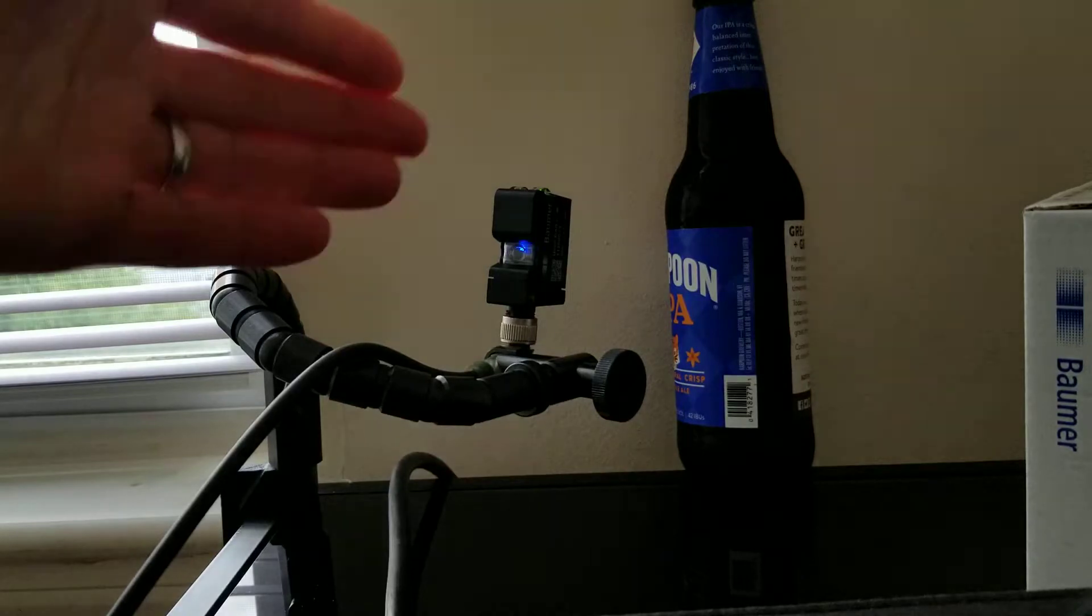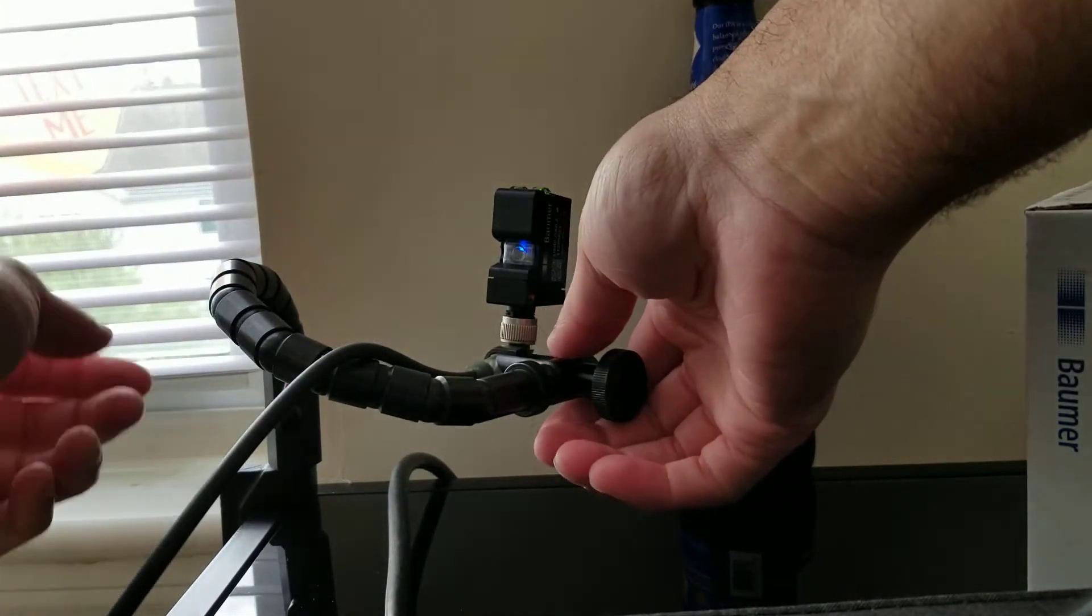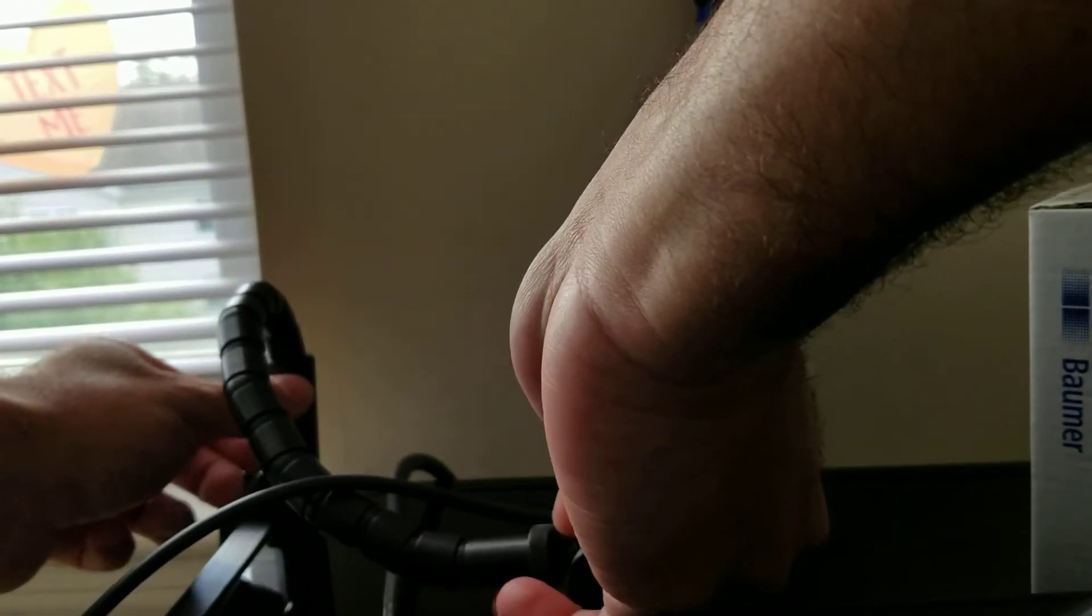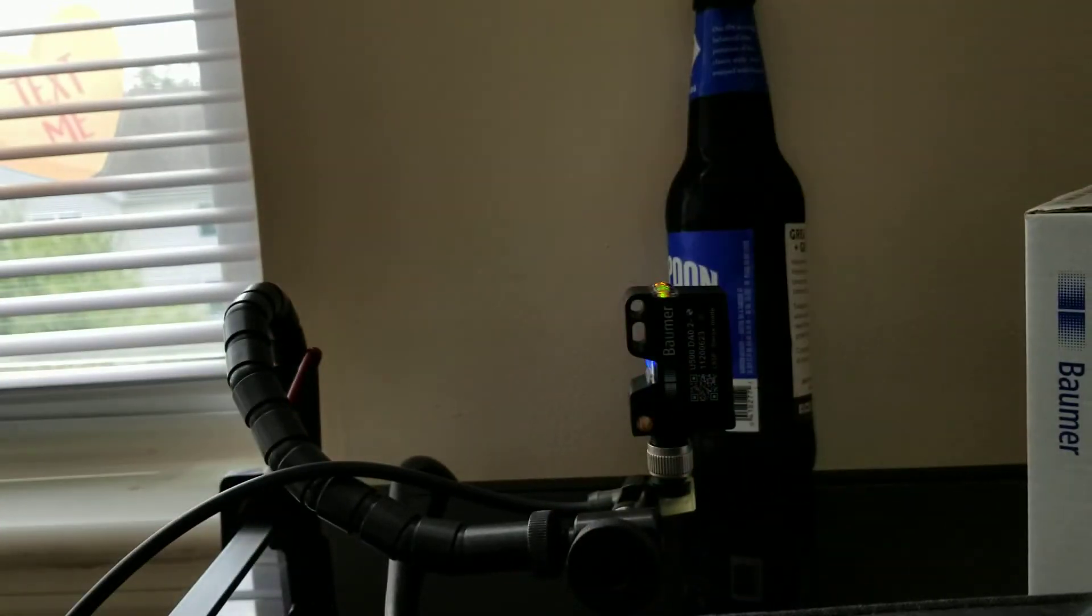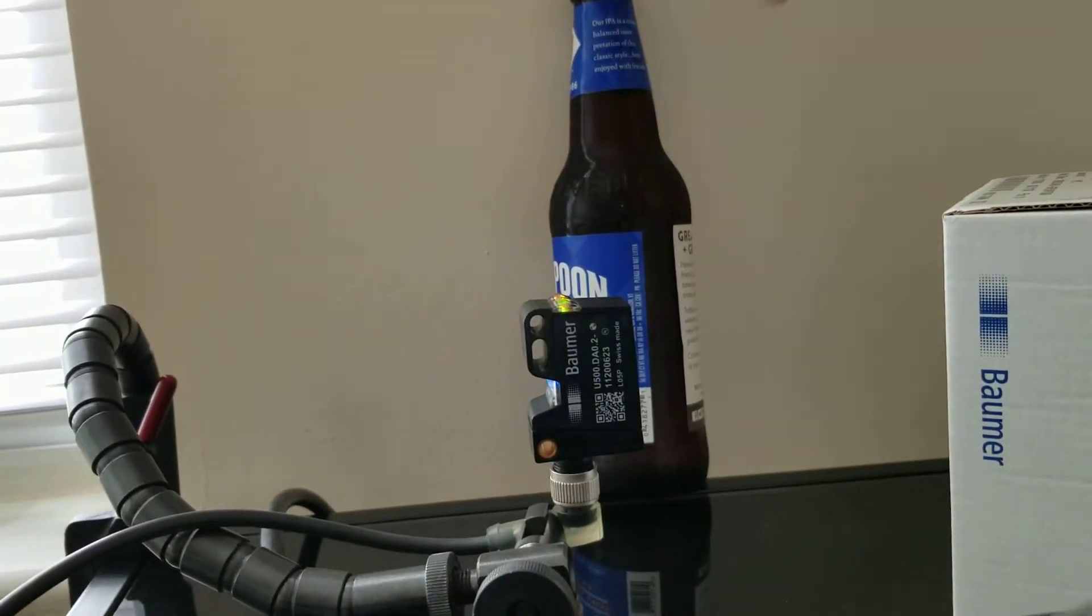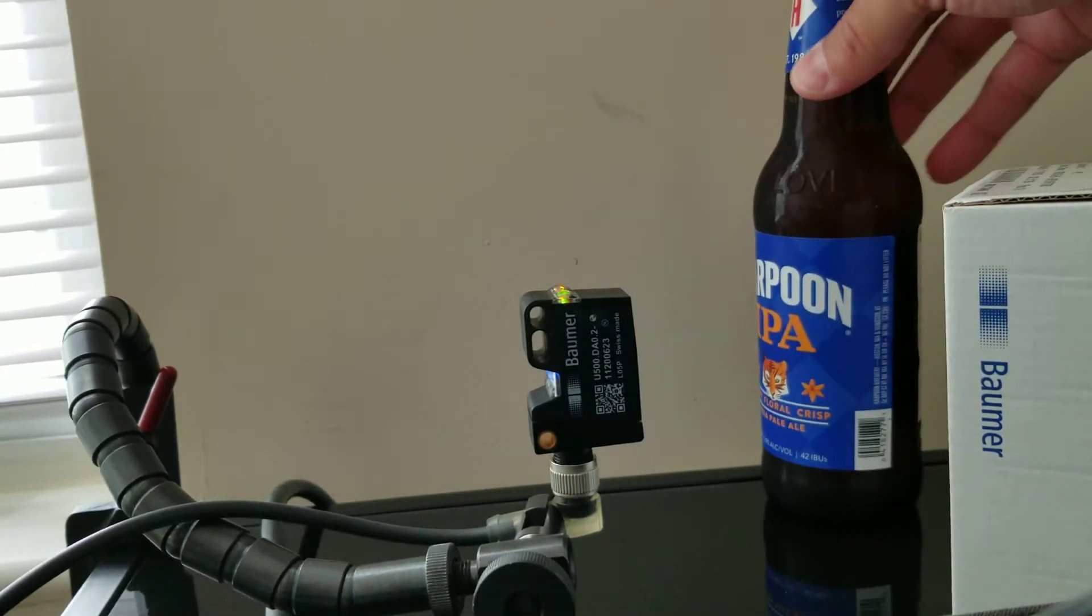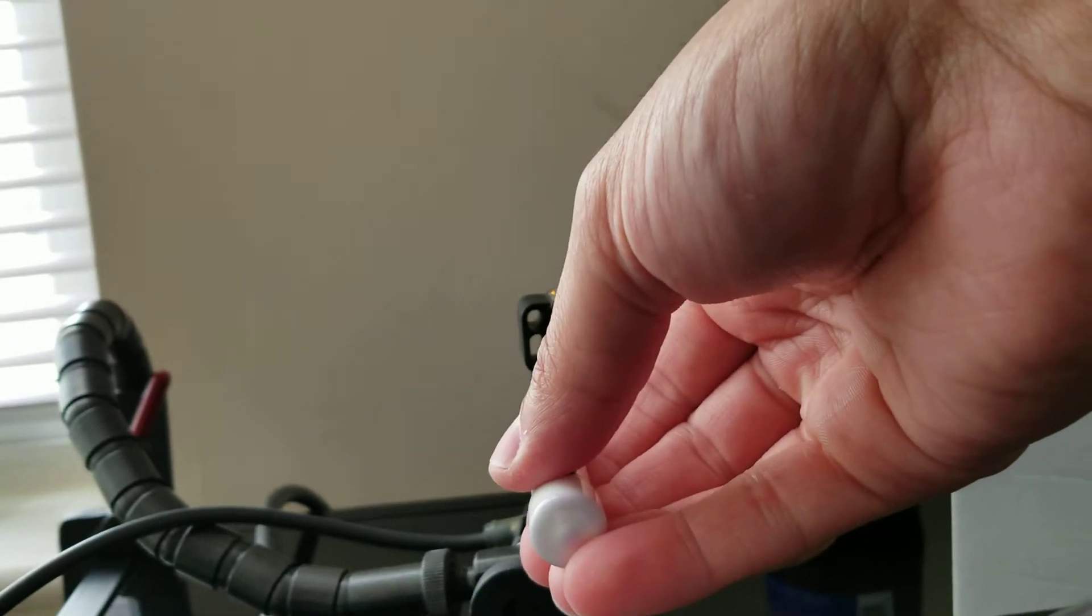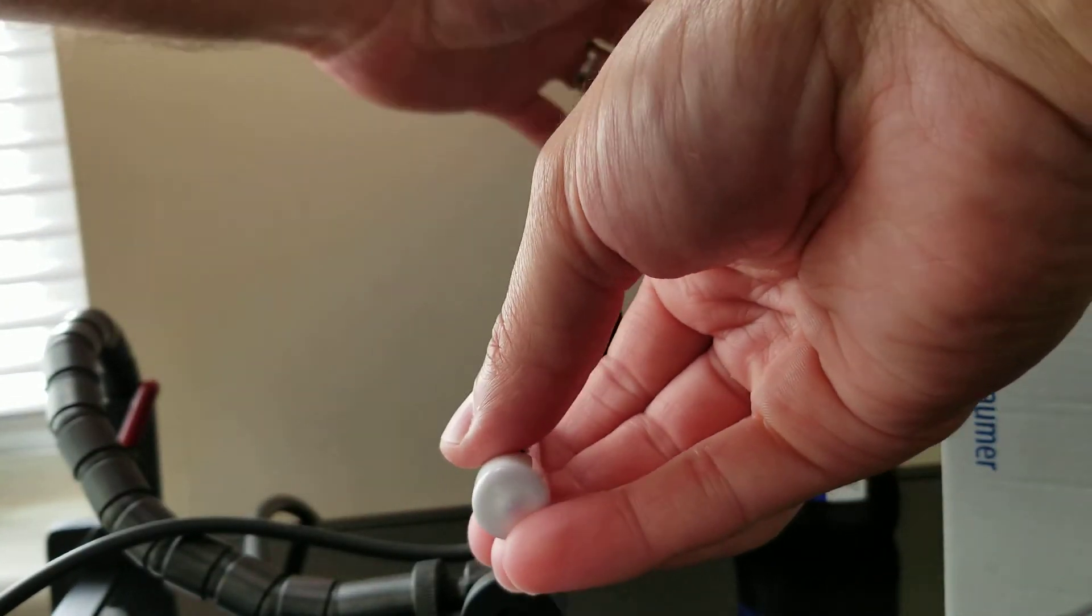So if we can't get the sensor back any further, what can we do? One thing you can do with an ultrasonic that's a lot easier than it is with photoelectric is take the sensor and mount it facing an object bent at a 45-degree angle, and then we should be able to teach it here. Right about there.